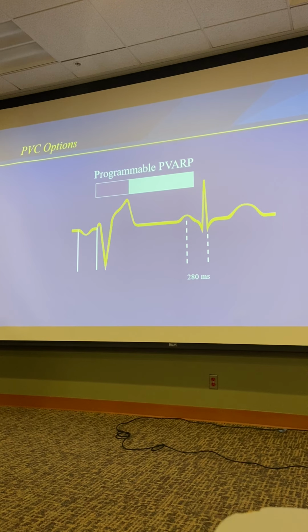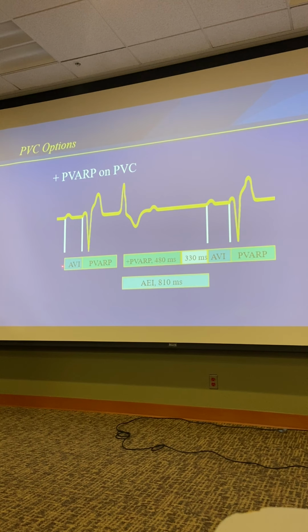This gets into the timing diagram. So this is an example here. Normally, after the ventricle fires, there's a period of time during which the atrial circuit can't respond to anything. When it sees a PVC, that is extended. So even though the signal got up to the atrium, going backwards through the AV node, it can't trigger a pacemaker-mediated tachycardia. This is called the PVC option on a pacemaker. If it's turned on, it should prevent a pacemaker-mediated tachycardia. If it doesn't, you can apply a magnet and terminate it.